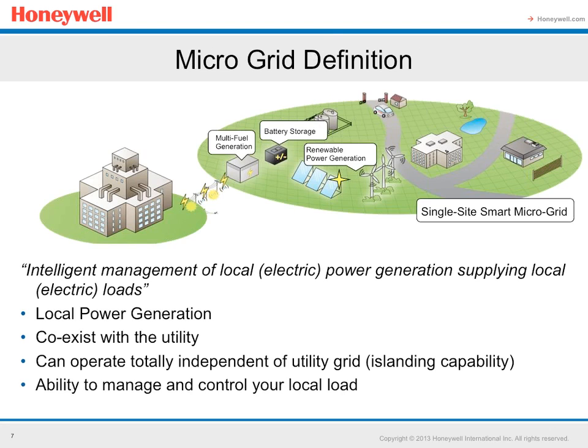There are certain parts common to all microgrids. One is local power generation that coexists with the utility. Some microgrids pull in a set amount of power continuously, but as soon as the grid becomes unstable, you switch to solely generated power locally that you control. That's called islanding capability. The other part is the ability to manage and control your local loads, which is a big part of this.